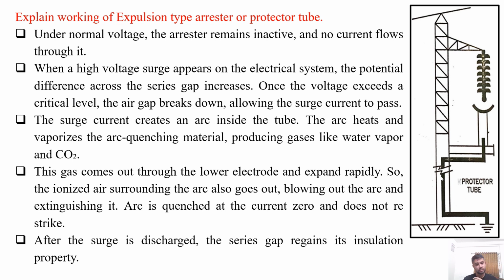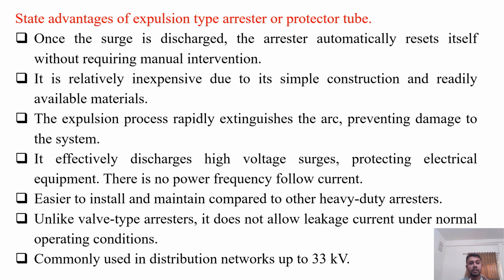After the surge is discharged, the series gap regains its insulation property and the arrestor returns to its previous state, which is under normal voltage condition, inactive or not in working state. So this is how the expulsion type or protector tube type arrestor works. State the advantages of the expulsion type arrestor or protector tube.